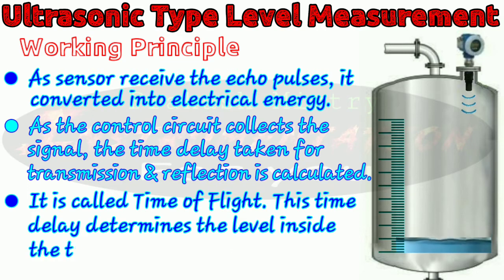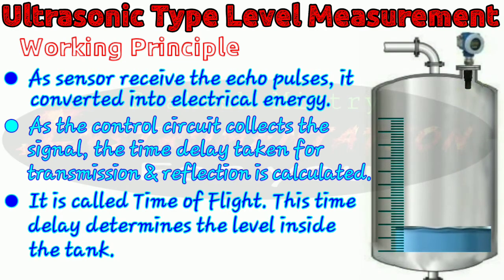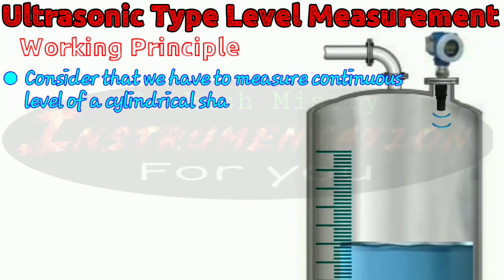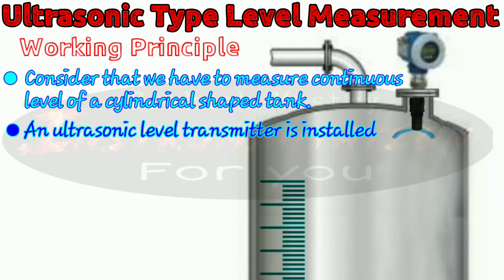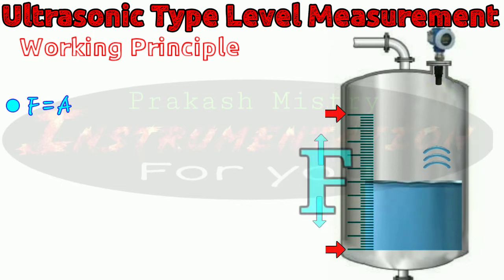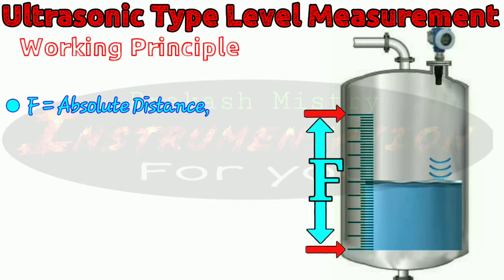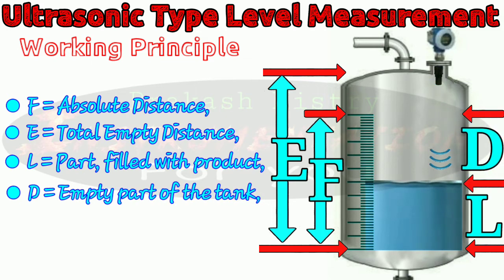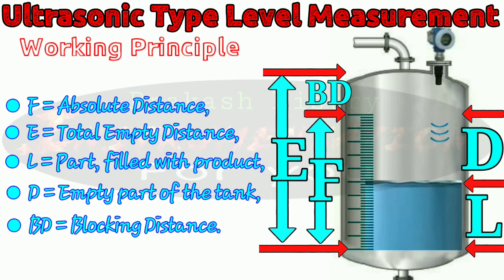This is the working principle of the ultrasonic level measurement instrument. As the control circuit receives the reflected echo pulses, it calculates the time of flight and gives the level indication. Consider that we have to measure the continuous level of a cylindrical shaped tank. The ultrasonic level transmitter is installed on the top of the tank. Here F is the absolute distance — the distance in which the level is to be measured. The downside is 0% level and the top side is 100% level. E is the total empty distance between the mounting flange of the sensor and the lowest measurable level, meaning 0% level. L is the part filled with the product, D is the empty part of the tank, and BD is the blocking distance.